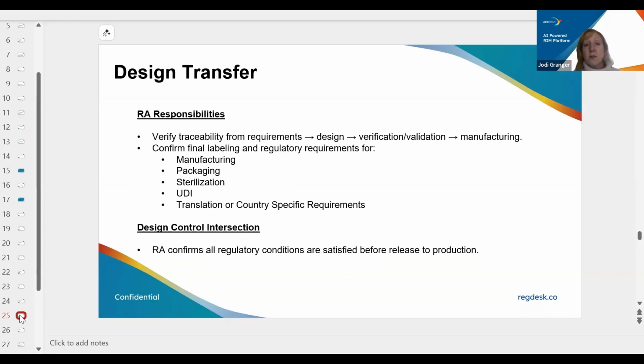For the design transfer, this is where you're moving from having your design, you've completed your verification and validation piece of it, and you can move into manufacturing. So regulatory will want to confirm the final labeling and regulatory requirements that will be moved into packaging or into manufacturing. They'll want to ensure that your packaging design, your sterilization, UDI, translations, all of that has been factored in before the formal transfer to manufacturing.